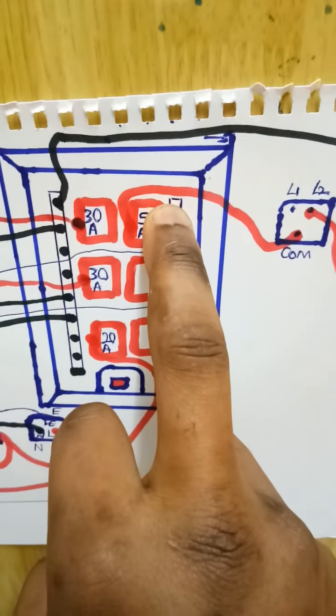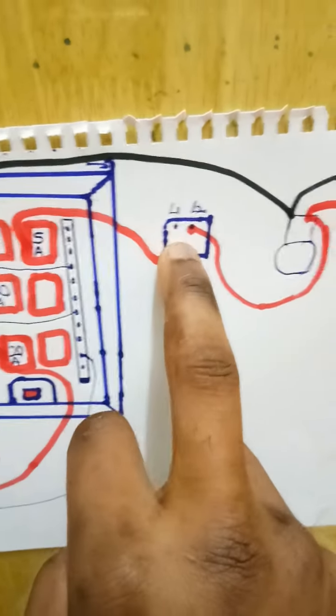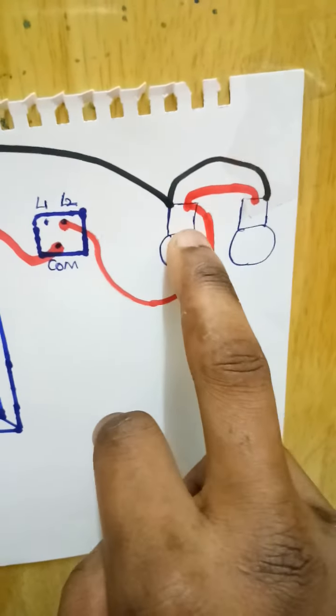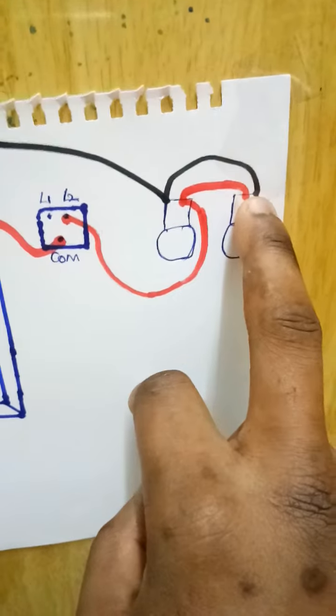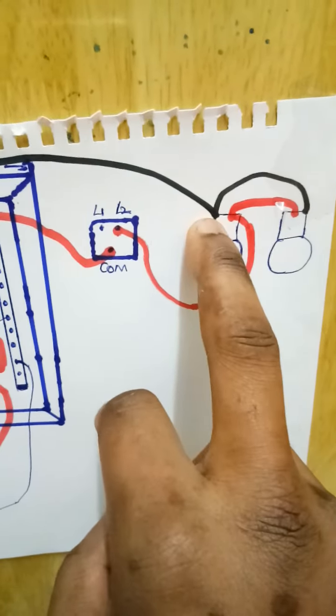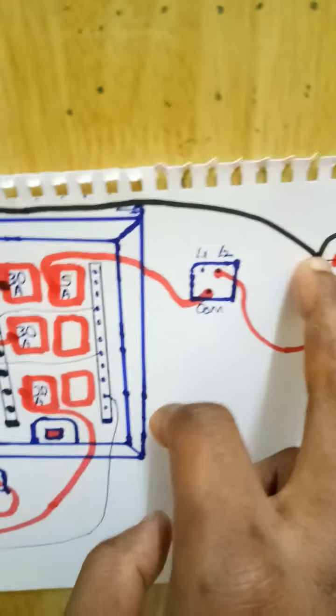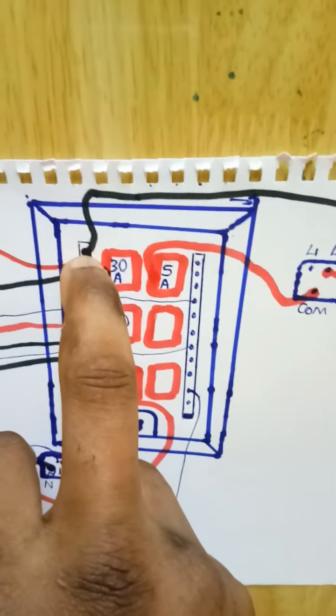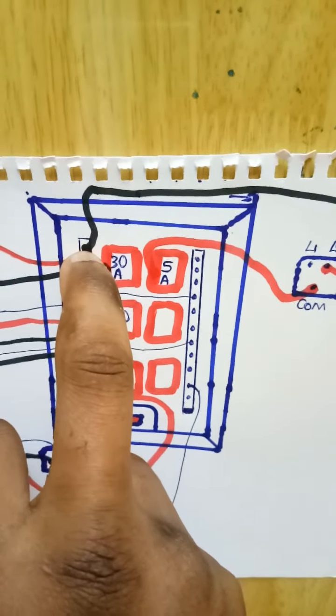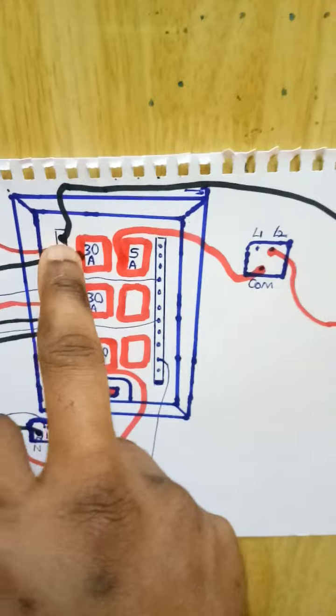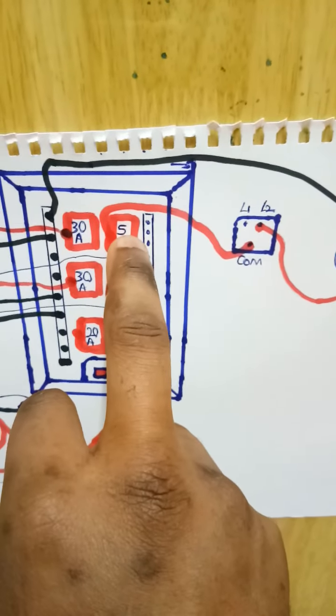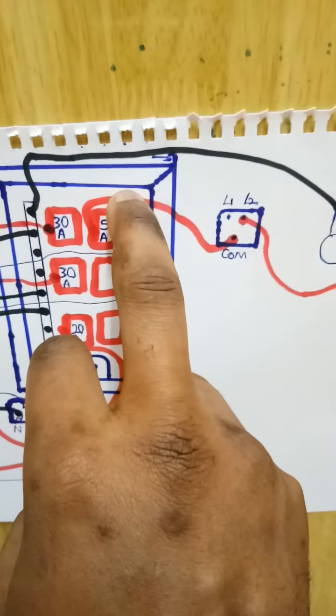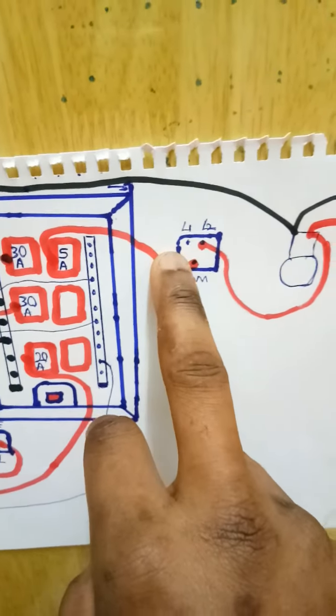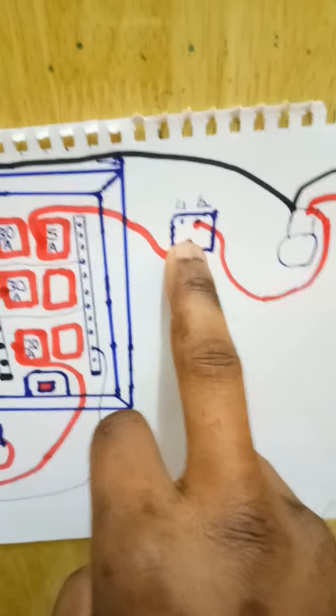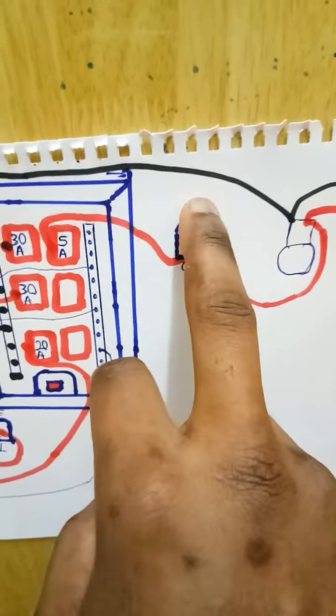This 5 amps is for the lighting point. As you can see, this is a 1-gang switch, and these 2 lighting bulbs are connected together. The red wire, the live wire, are looped together. The neutral is connected together. The neutral from the lighting points comes directly to the neutral rail. But here the live wire comes from the circuit breaker to the switch, and this point and this point are not connected, except when you flip the switch, they will now be connected.